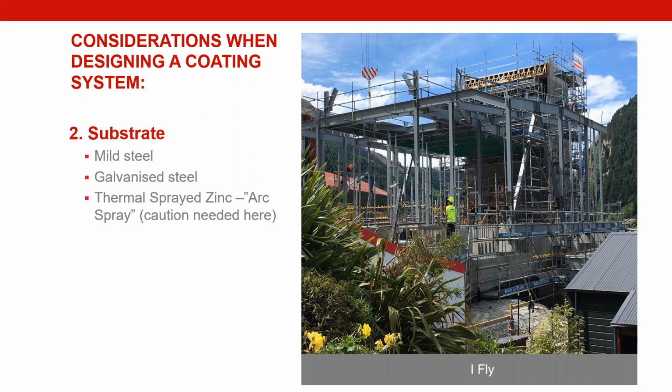It depends on the substrate that you're dealing with, giving you different properties. Your fireproofing materials are generally limited to carbon steel and those associated with the metallized coatings over the top of, whether it be galv or thermal spraying, but we're predominantly talking about mild steel. All the testing is done on those materials, so it only applies to those materials.